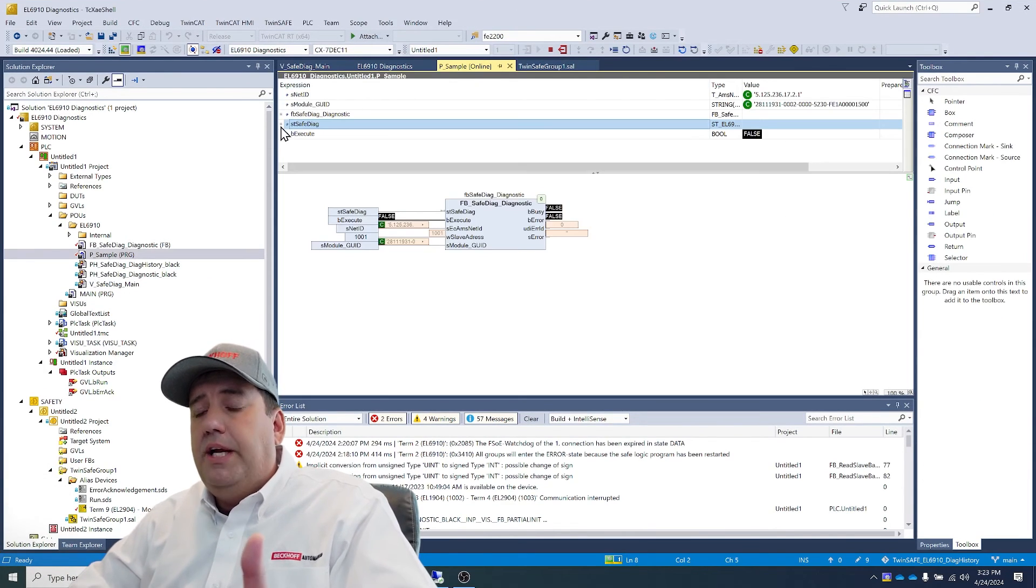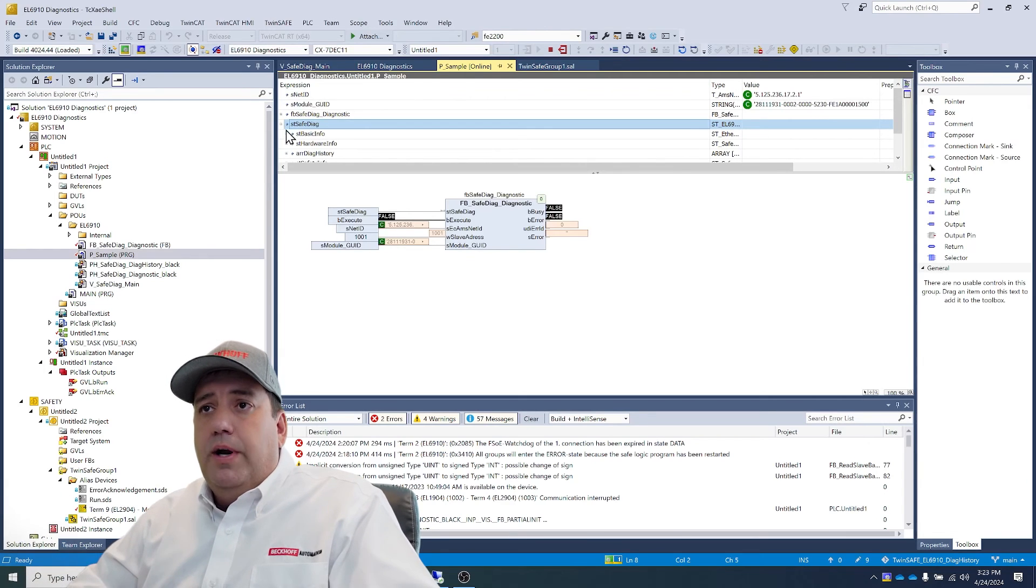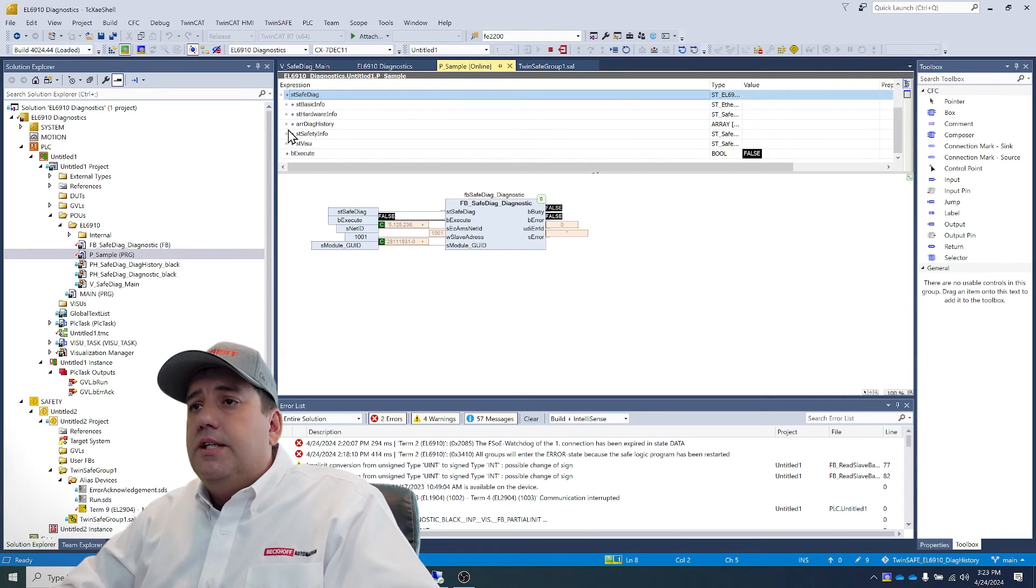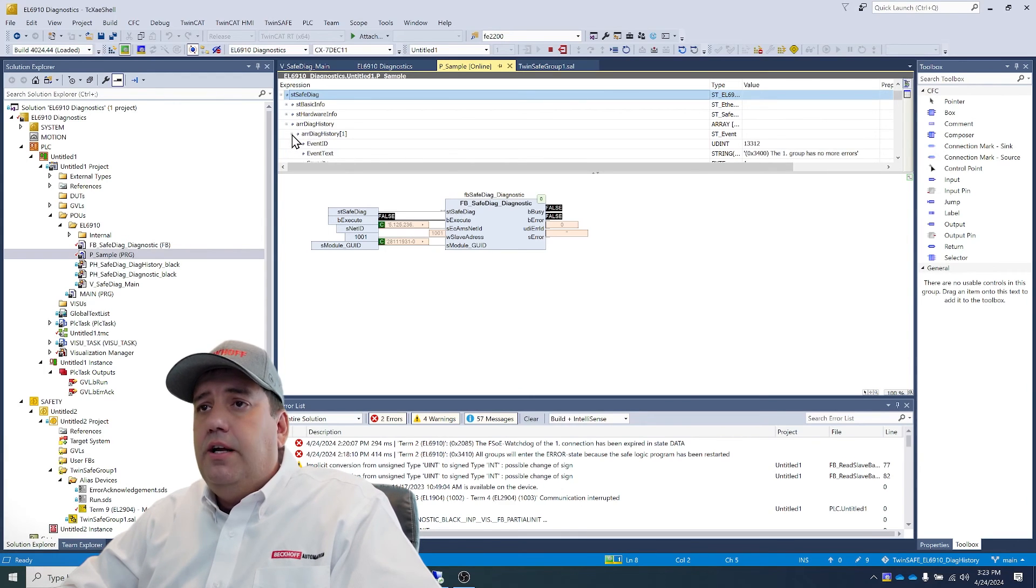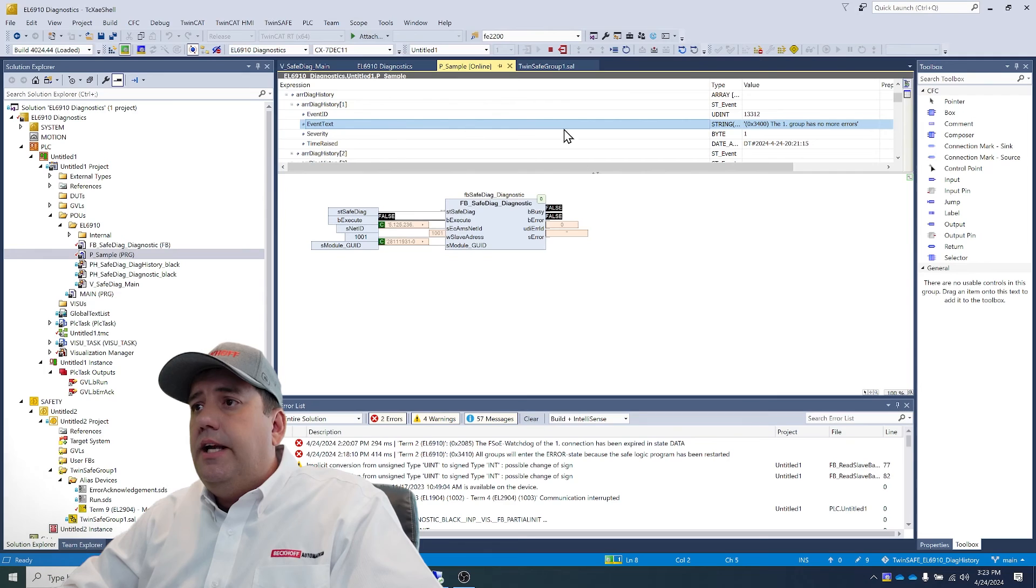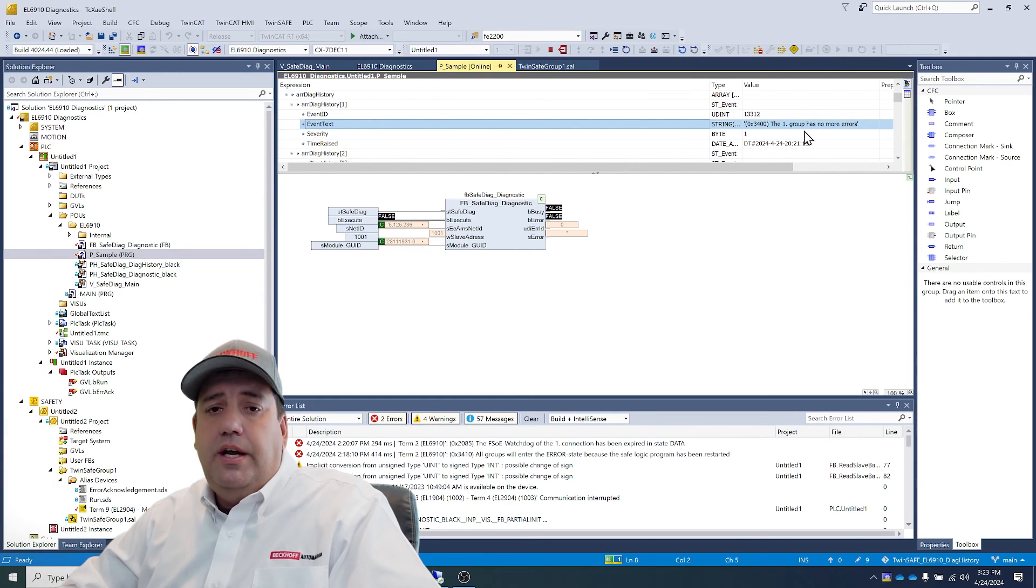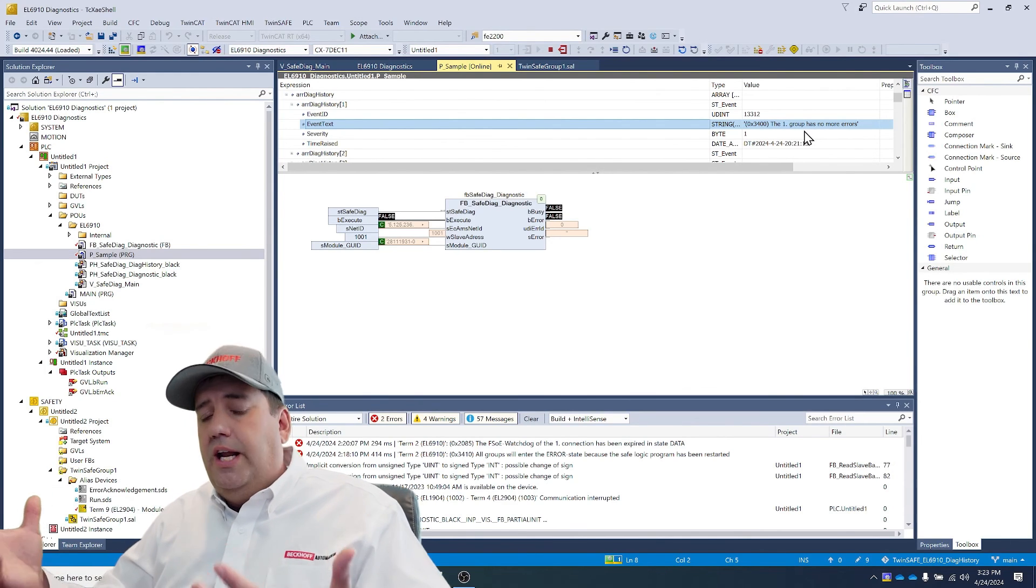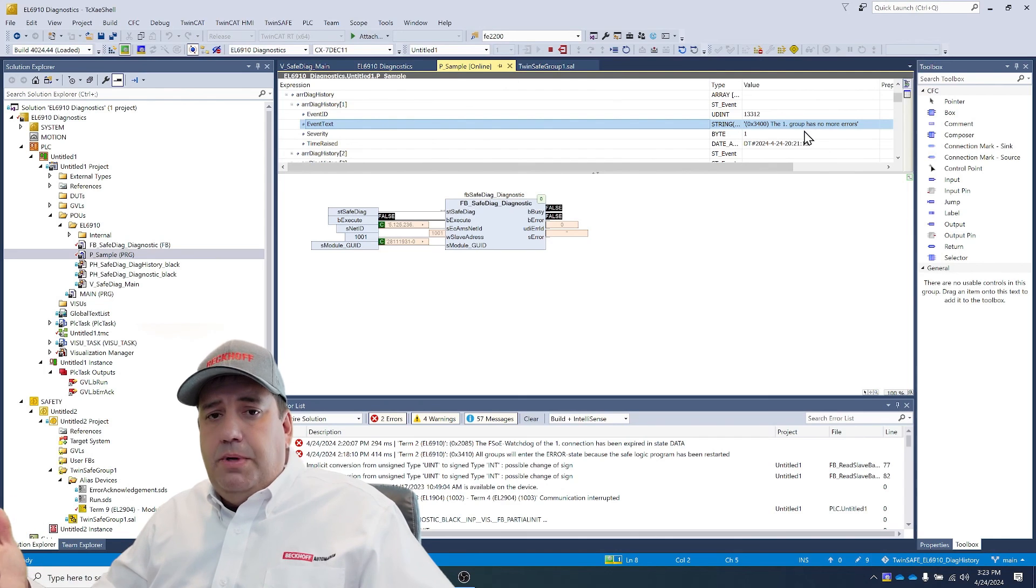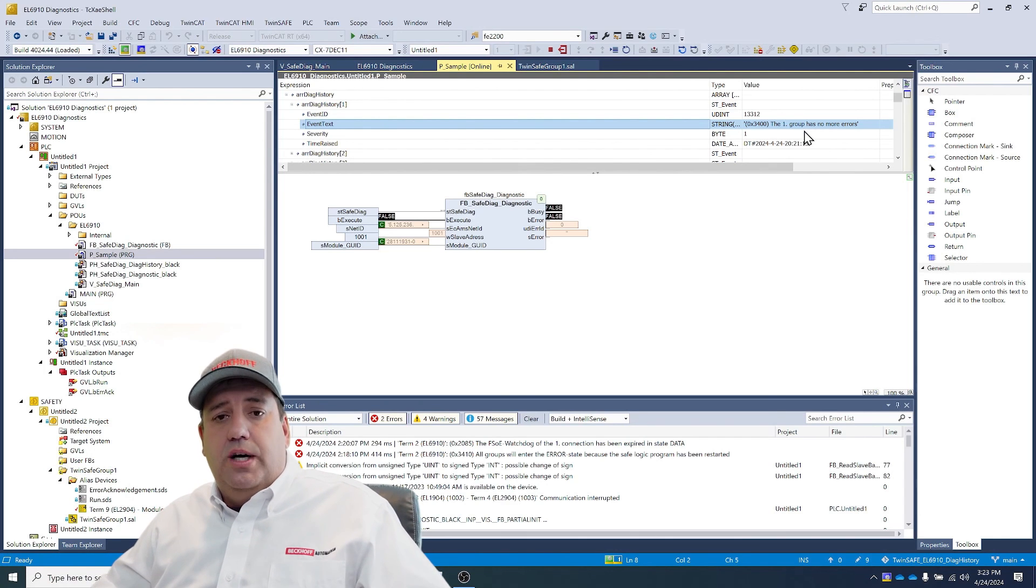Now, I said that these were in the PLC program. Right here, if I go into this safe diagnostic and I go into the array of the diagnostic history that's been created with this function block, I can see the event text right here in this register. So I can take this text, I can take the event IDs, and I can use that any way that I want within my PLC program or send it somewhere else.